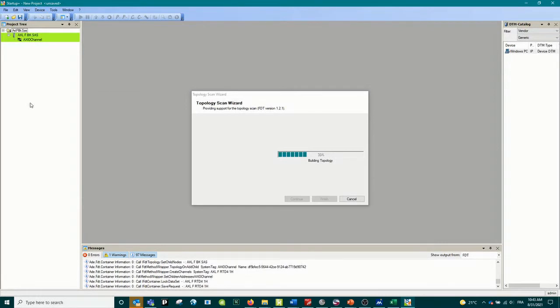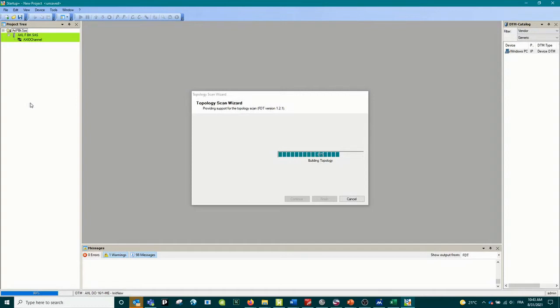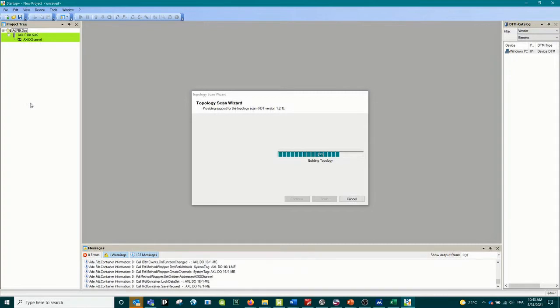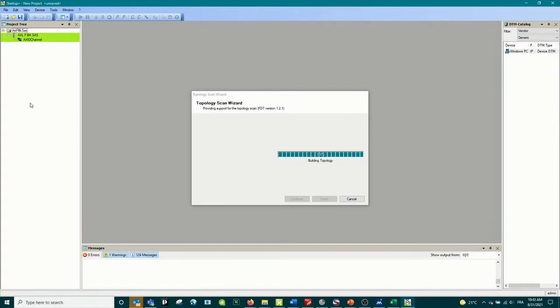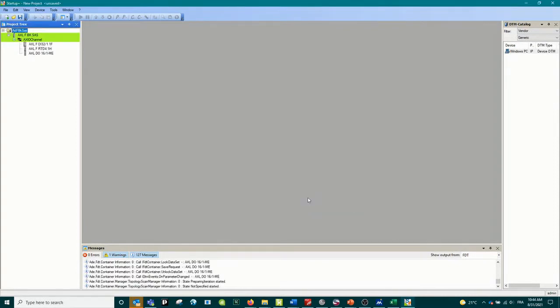The two steps we will do together today: first we will configure the RTD input card because those analog RTD cards need to be configured - we need to enter some parameters according to the sensor we are connecting to it. The digital input and output require no configuration. After that we will do the IO check. IO check is a way to be able to read all the inputs and force all the outputs without the need of adding a master or a PLC attached to it.